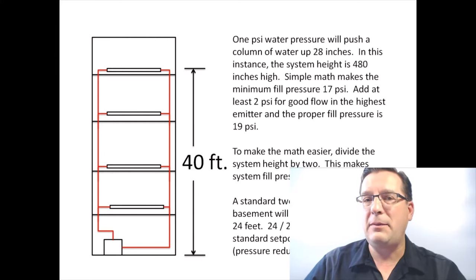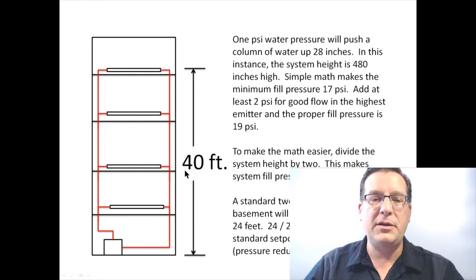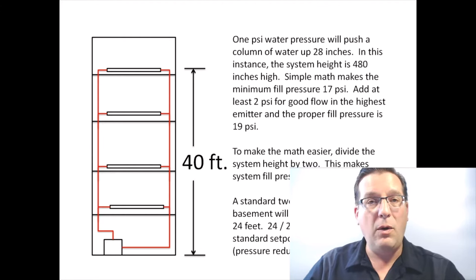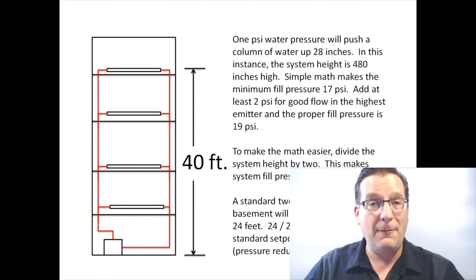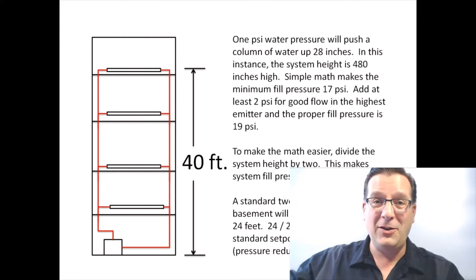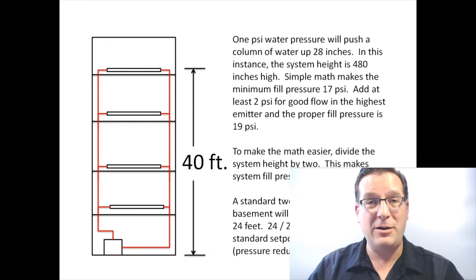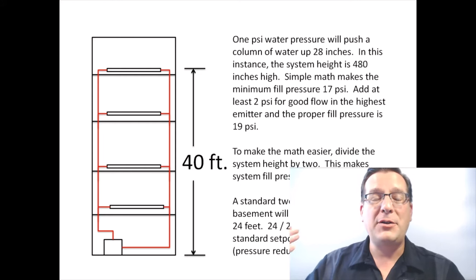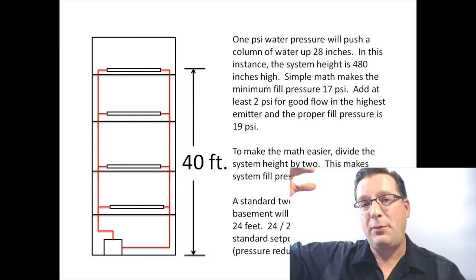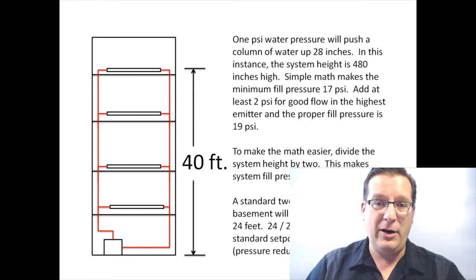I like to make the math easy: just take your system height in feet and divide by two. Because 28 inches is really close to 24 inches, which is two feet, it's much easier to do the math that way. 40 feet tall divided by two equals 20 PSI cold fill pressure. That's enough to fill to the top plus the little extra needed to make sure you're still pressurized at the highest emitter.